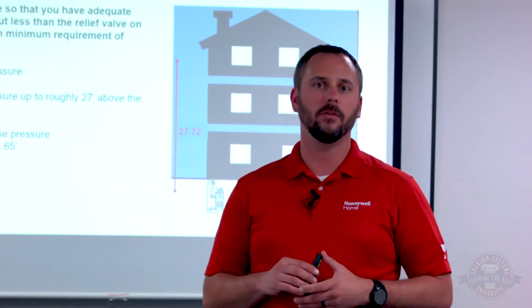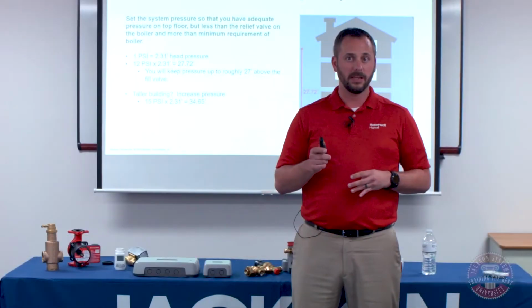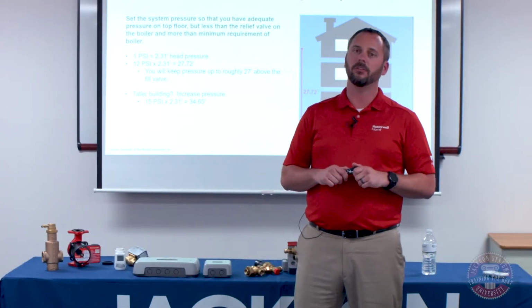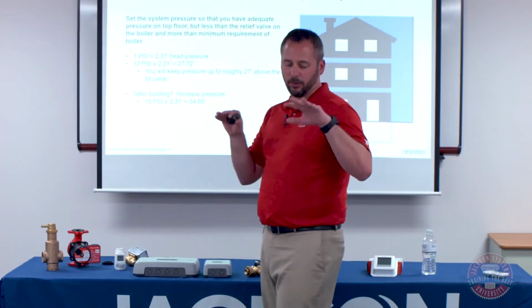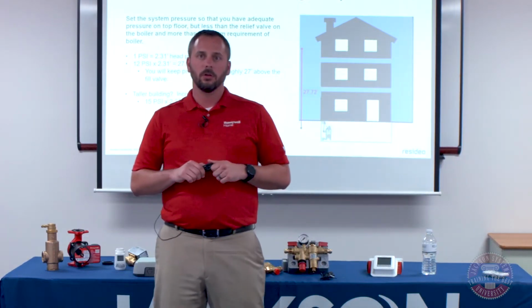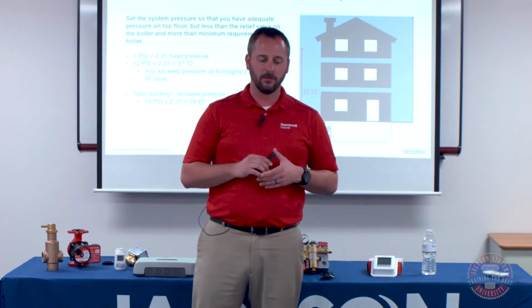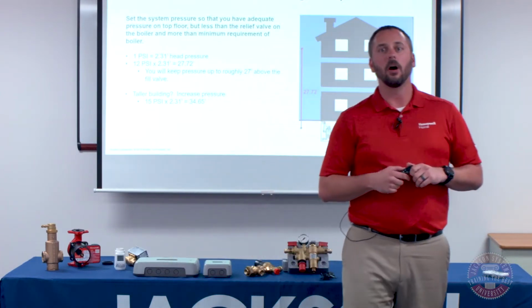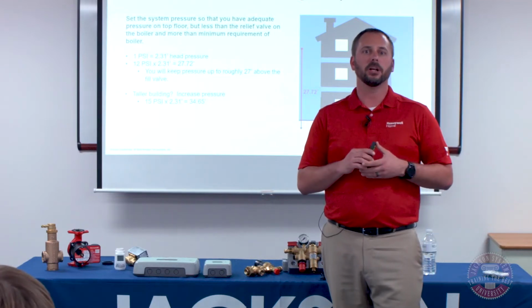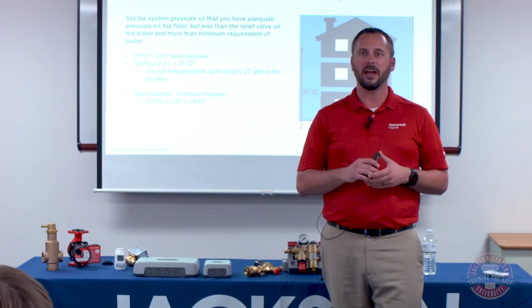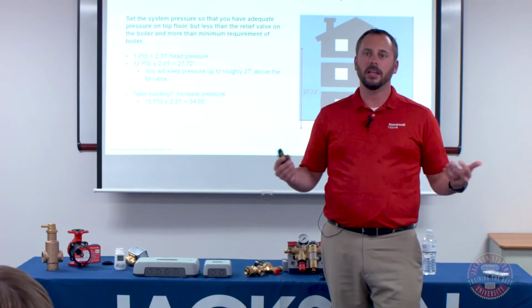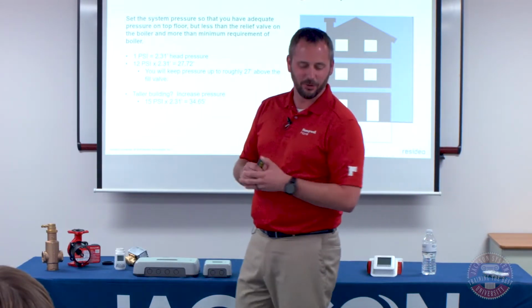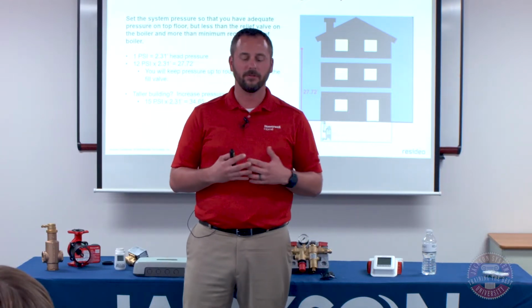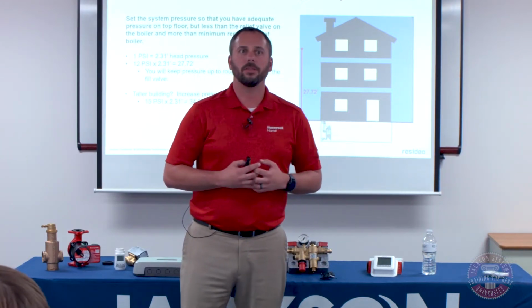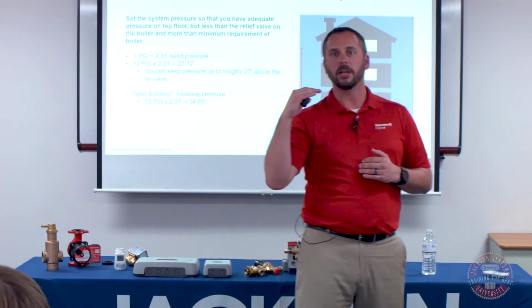So with this being said, in this example, that 12 PSI, so let's say we've got the boiler down in a basement, we set it at 12 PSI. What that's going to do is give us the equivalent stagnant pressure at the top of 27 feet. So that means you will still have pressure at roughly 27 feet tall. So what do you do if the building's taller than 27 feet? You increase your pressure down at the basement. So if you were to increase that to, say, 15 PSI, I've already done the math here, that's going to give you the capacity to handle roughly a 35-foot tall building. So the one thing to keep in mind, you're working with gravity when it comes to static pressure.